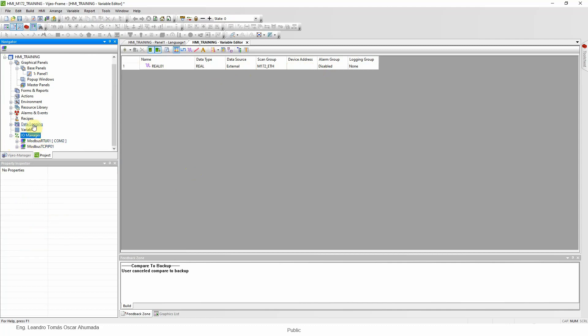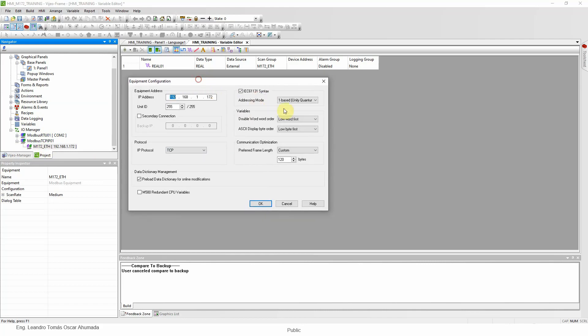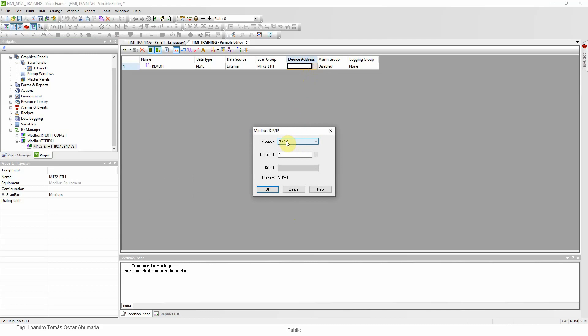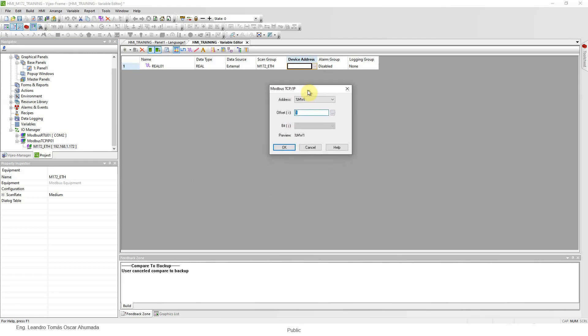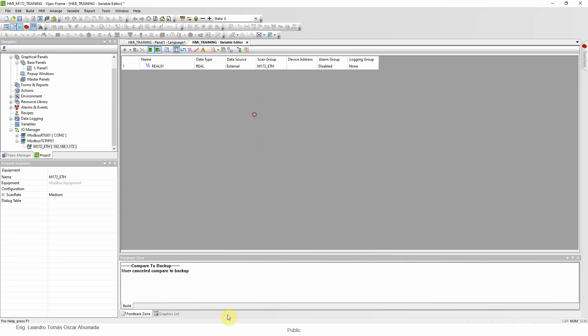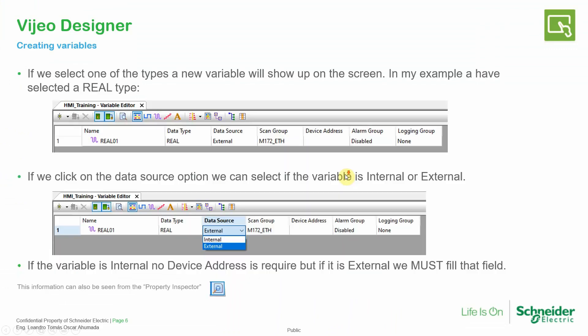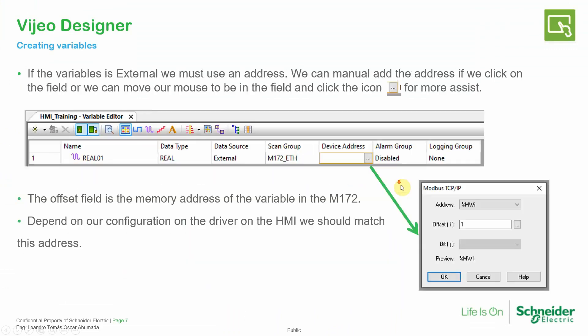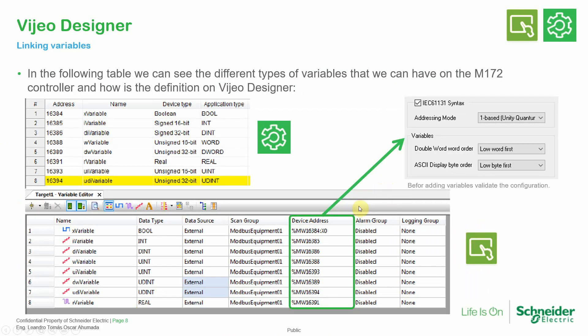So now if this variable comes from the PLC, we need to first double-check how we have defined our device on the network, in this case the PLC. If we have this configuration for this PLC, we just need to use this %MW and then the address that we have on the PLC side.